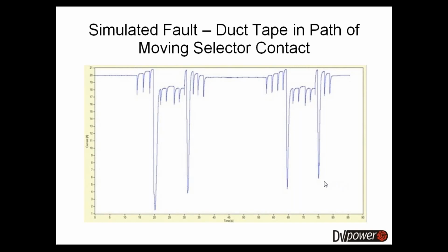And by the time the fourth operation is done, you can see that the current drops down to 6 amps. So you are measuring 4 different ripples in 4 cases where the transition resistance in the circuit during the operation is different.